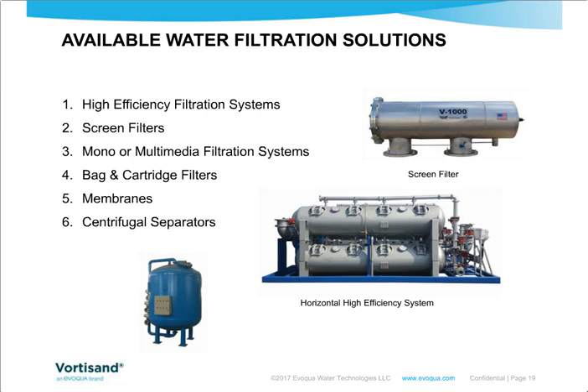Bag and cartridge filters are another great solution for filtering down to that 1 micron level. But again, there's a cost associated with that. Yes, it's a low capital cost, but given the amount of filters required to maintain your performance, you could cause a tremendous amount of operational cost and change-out frequencies. Membranes are another solution on the market, but that's focusing more on dissolved materials and requires a tremendous amount of capital investment. So it might be a little bit over-engineered for a cooling tower or another type of low, or I should say high purity application.